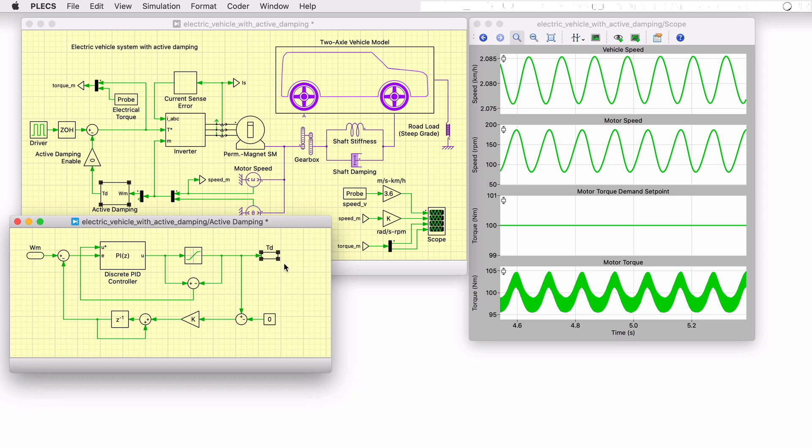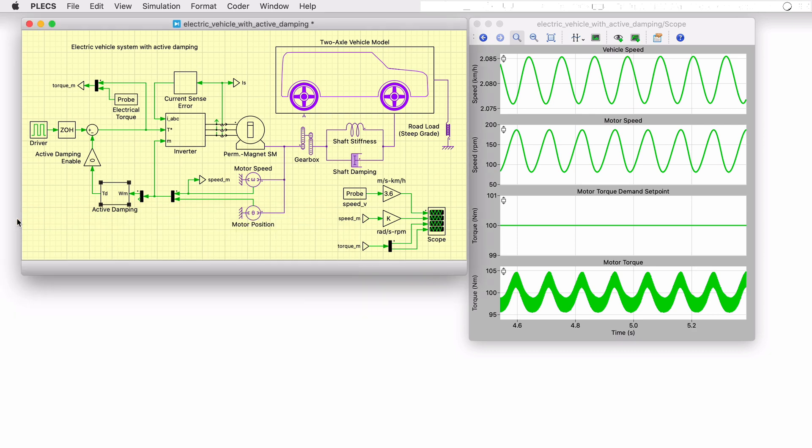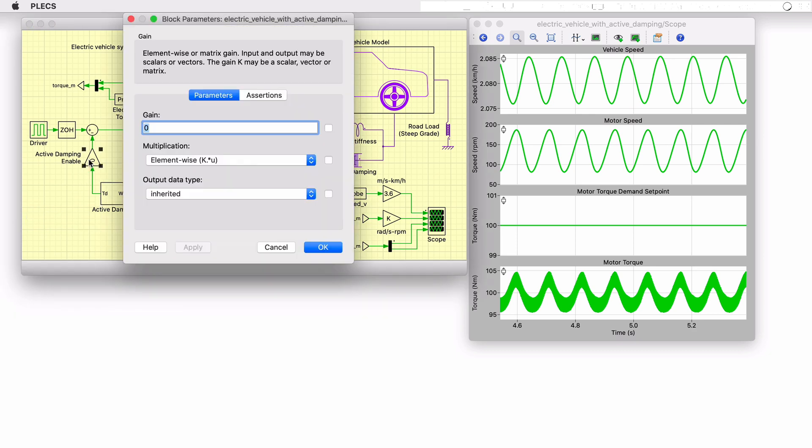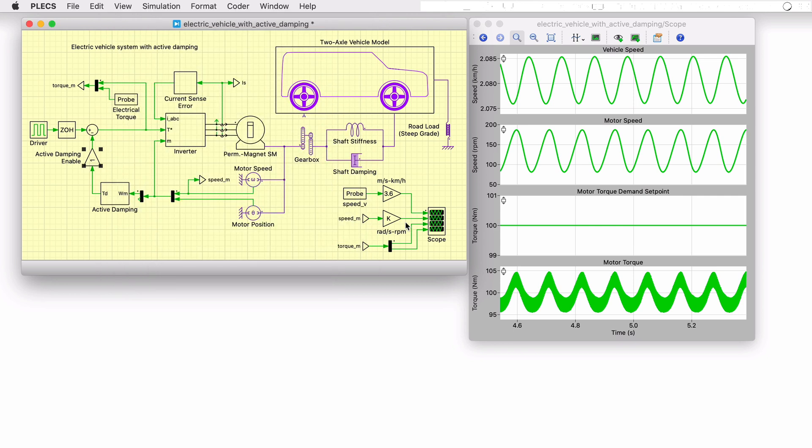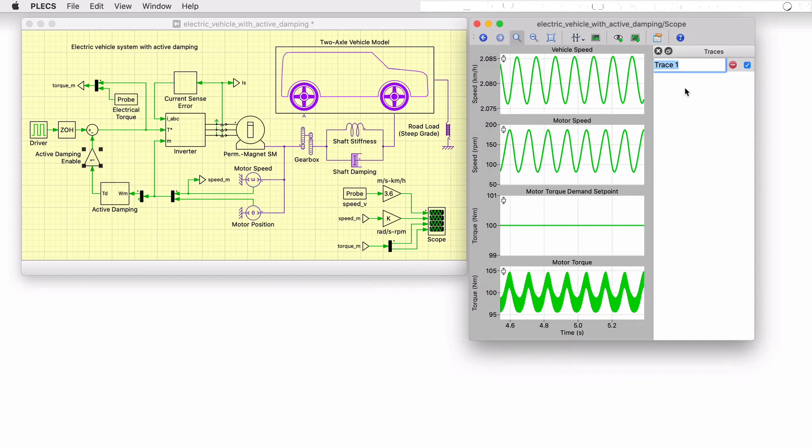The correction torque, along with the torque demand of the driver, is used to modify the torque setpoint that is fed into the torque controller. If we now enable the active damping method to adjust the torque demand signal, the result is a significant reduction in the wind-up effects and oscillations that occur without the algorithm.